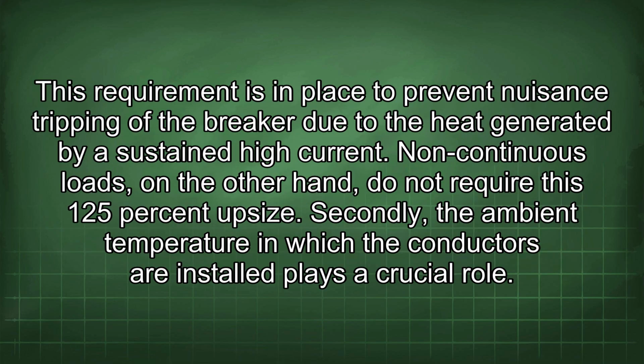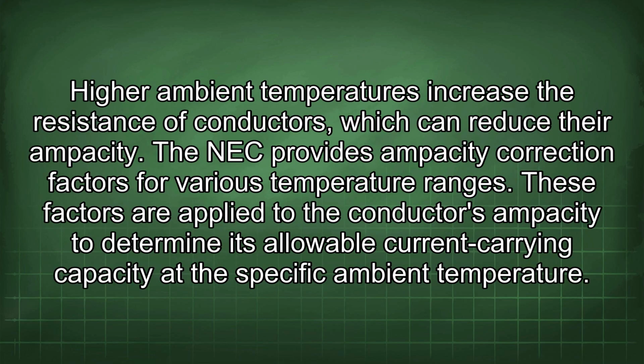This requirement is in place to prevent nuisance tripping of the breaker due to the heat generated by a sustained high current. Non-continuous loads, on the other hand, do not require this 125% upsize. Secondly, the ambient temperature in which the conductors are installed plays a crucial role. Higher ambient temperatures increase the resistance of conductors, which can reduce their ampacity.